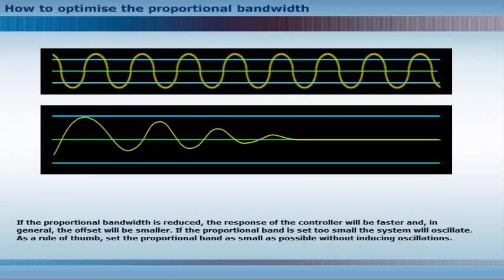If the proportional bandwidth is reduced, the response of the controller will be faster and, in general, the offset will be smaller. If the proportional band is set too small, the system will oscillate. As a rule of thumb, set the proportional band as small as possible without inducing oscillations.